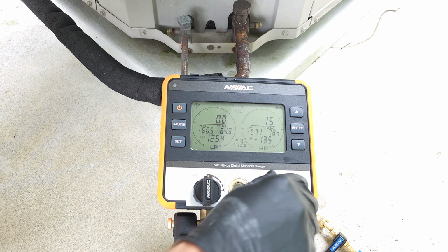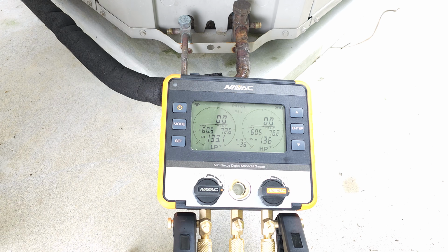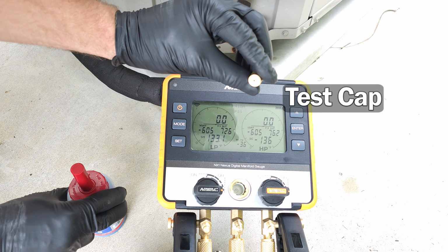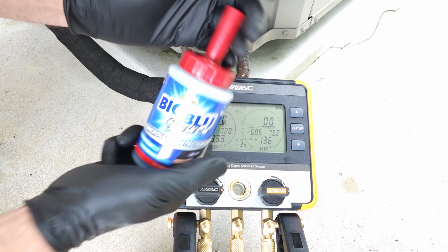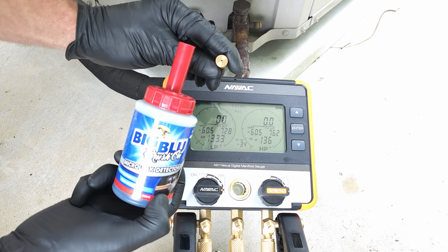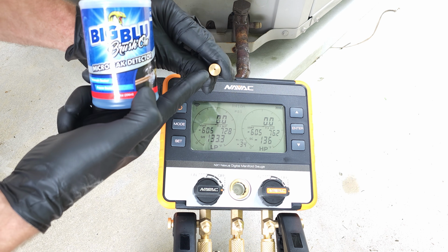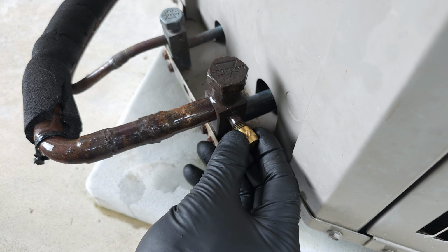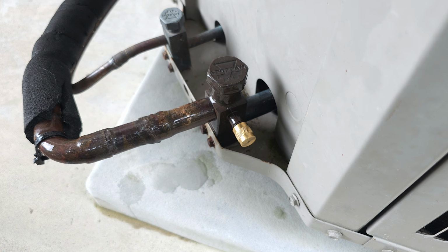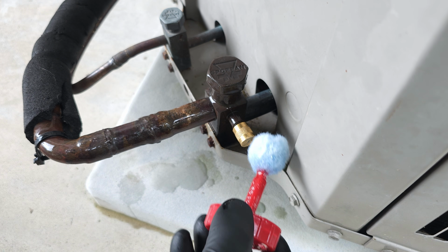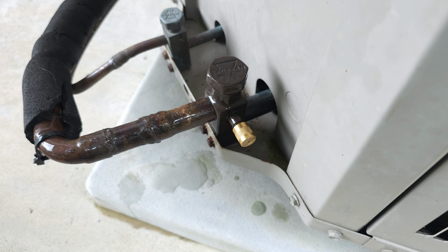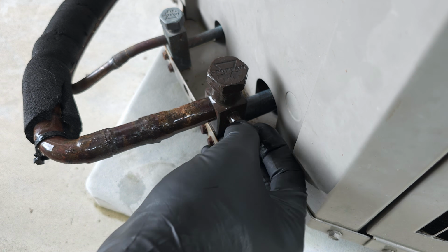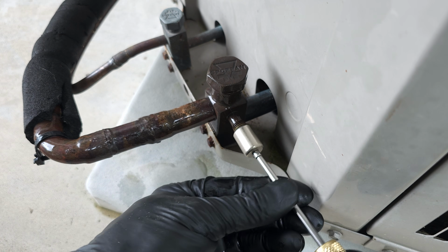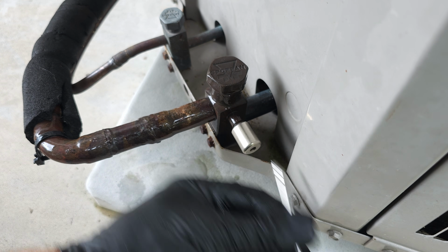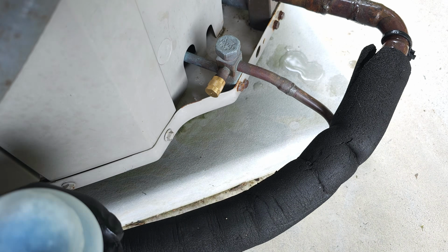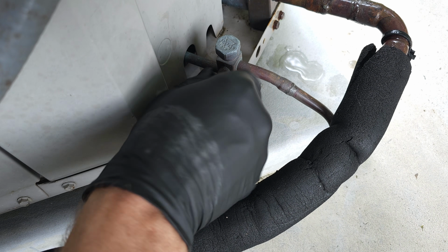And we're going to go ahead and shut these valves again, and we can leak check over here at the ports. To leak check, we're going to put one of these little test caps on the ports, and we're going to use our big blue leak detector. We're going to make sure that after we put this test cap on, after we add bubble leak detector, there are no bubbles. So that one's good. We can go ahead and put our locking caps on. So no bubbles are forming there, so we're good there.